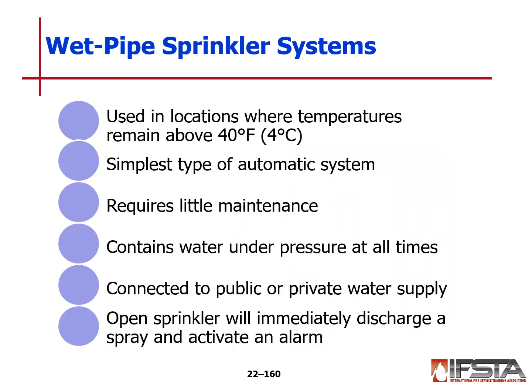Wet pipe systems are used in locations or areas where the temperatures remain above 40 degrees Fahrenheit at all times. This is the simplest type of automatic system. It requires little maintenance. It does contain water under pressure at all times. These are connected to public or private water supplies, and an open sprinkler will immediately discharge a spray and activate the alarm.